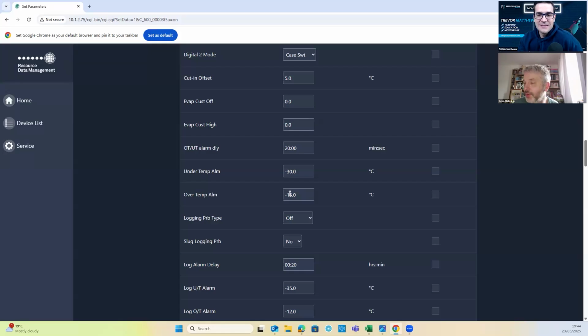So we all know we need to educate customers about what doors do, and we all know what realistically happens. So set it with some view to what the room's doing. If it's a deep freeze cold store that's going in once or twice a day, set it tight, because you want to know when that's going to break down. And if it's a massive room, it's going to have a huge amount of inertia on that temperature. So if it's got to -15, there's a problem. So set it tighter. A smaller room is going to lose temperature faster.